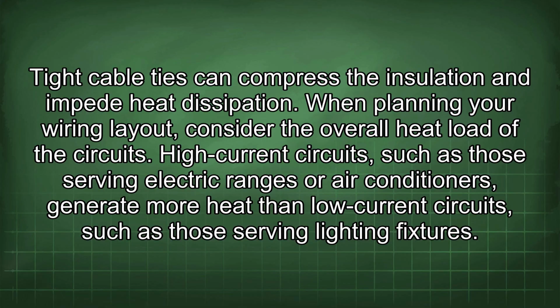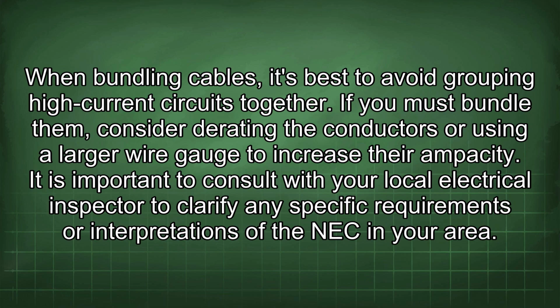When planning your wiring layout, consider the overall heat load of the circuits. High current circuits, such as those serving electric ranges or air conditioners, generate more heat than low current circuits, such as those serving lighting fixtures. When bundling cables, it's best to avoid grouping high current circuits together.